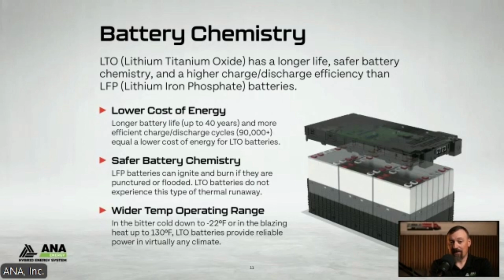The last one I thought was important to note here was a wider temperature range. LFP technologies a lot of times are going to require some kind of environmental control - you've got to make sure it's a certain temperature as far as warm and cold, so you might need heaters and HVAC systems to utilize the technology. LTO technology has a very wide operating range - negative 22 all the way up to 130 degrees Fahrenheit - it can safely and reliably operate.